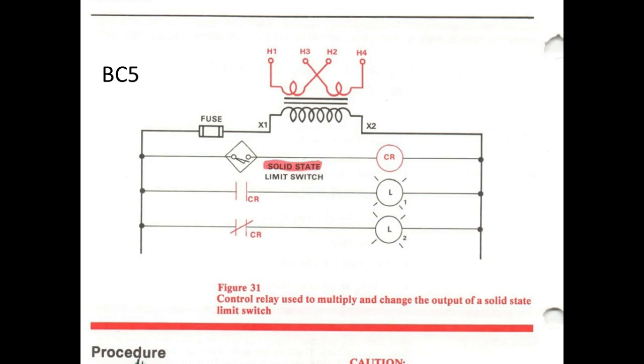So what we're going to do is try to run two different lights off of a solid state relay. The solid state relay's only got one contact, so we're going to sacrifice that one contact to bring in a control relay.